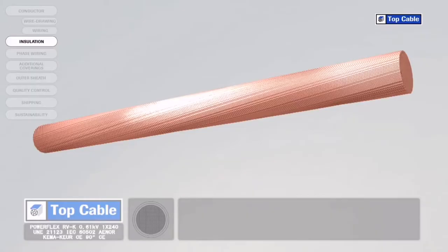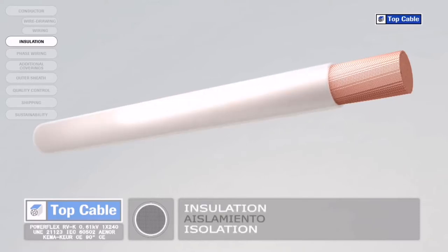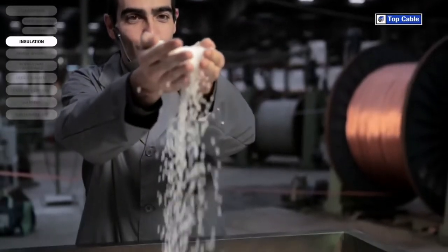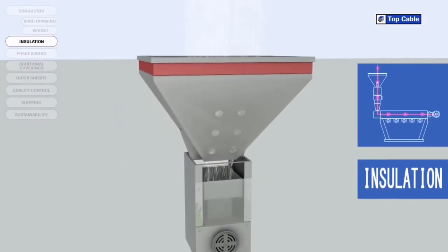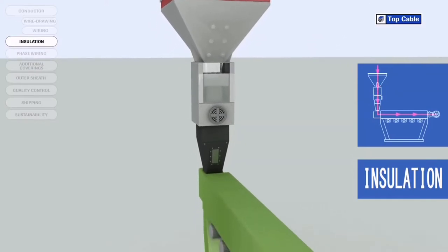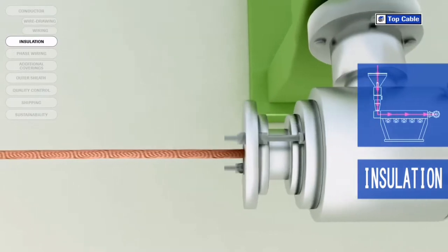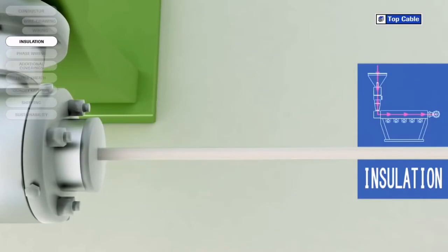The next process in the manufacture of electrical cables is the insulation. This is when we place an insulating cover over the conductor to prevent current leakages. The insulating material is added by a process of extrusion at high temperature. Several insulating materials may be used: PVC, EPR, XLPE, etc. Different insulation materials may be used depending on the characteristics of the cable required.